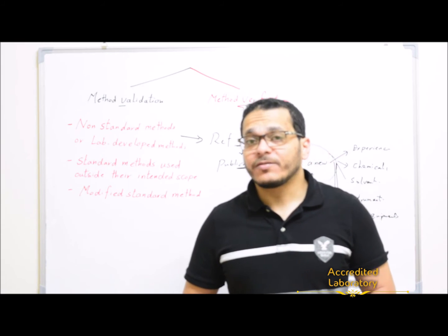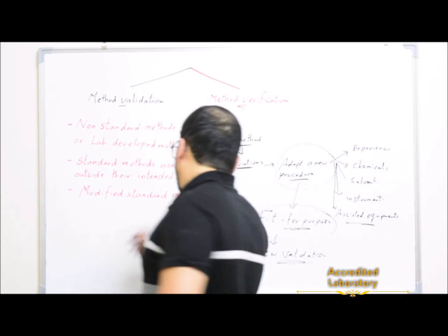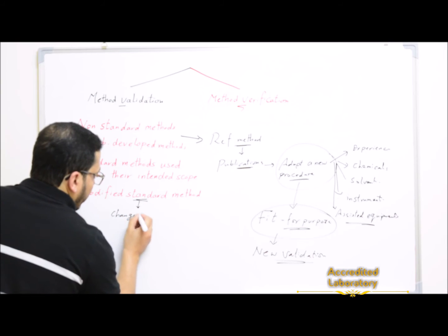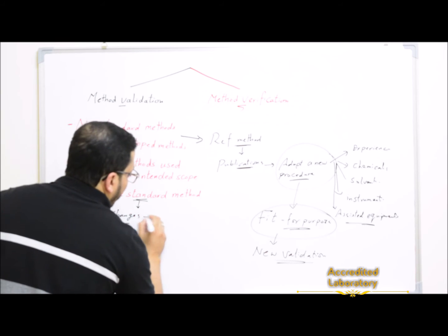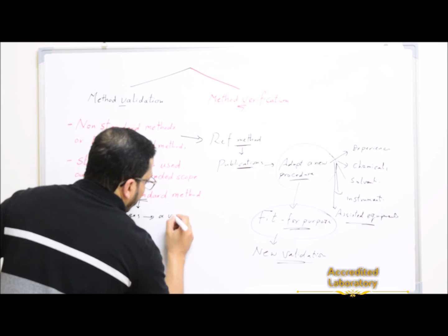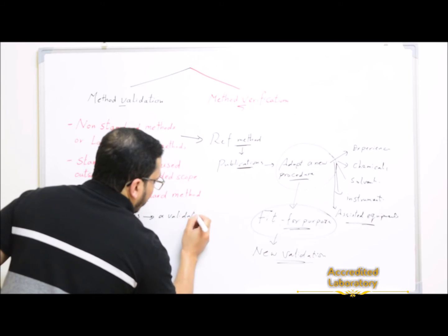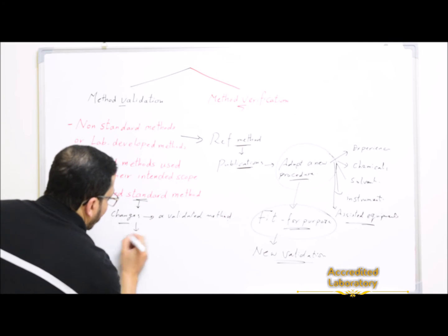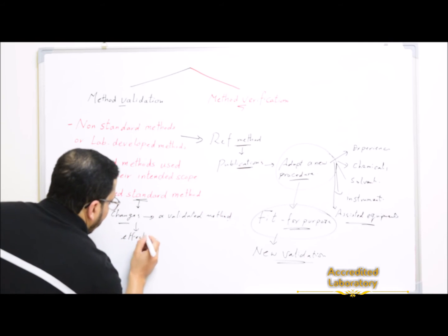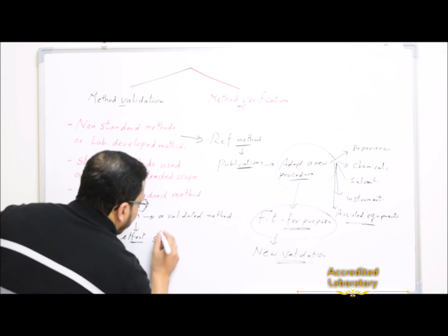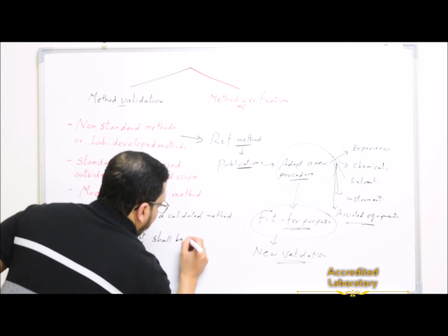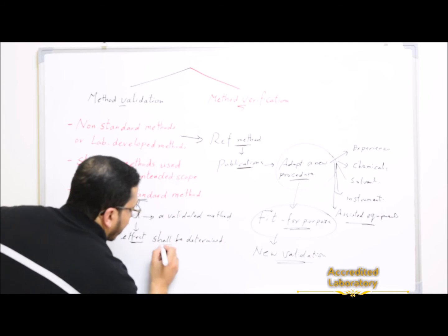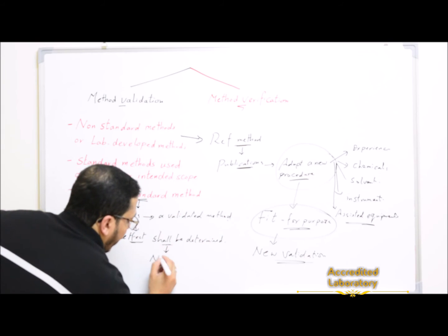Also, in case of modified standard methods, when a change is applied to a standard method, a validated method, the effect of these changes shall be determined, and if required, you can make new validation.